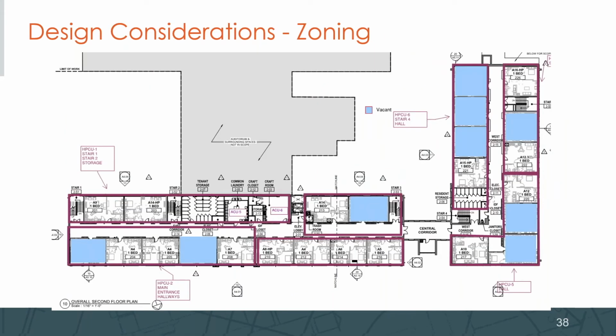So here's an actual project that I worked on. It was a historic retrofit project in Climate Zone 5. Each of these purple boxes you see is a zone, right? They tried to zone each one according to solar orientation, so that if they needed to change one condenser to cooling versus the other to heating, in one wing or the other, they could do that because they did not have energy recovery in the system. So you can't do the simultaneous heating and cooling.